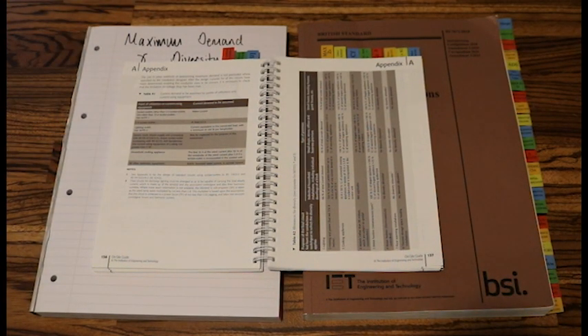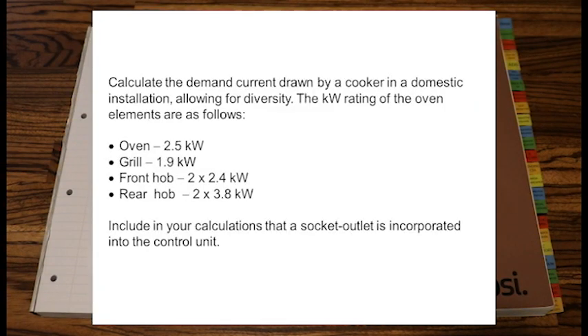So on your screens, you will see the question. It says, calculate the maximum demand current drawn by a cooker in a domestic installation, allowing for diversity. The kilowatt rating of the oven elements are as follows. And we've got an oven as 2.5, a grill 1.9. There's a front hob, and there's two of those, 2 times 2.4, and two rear hobs at 3.8, all in kilowatts.